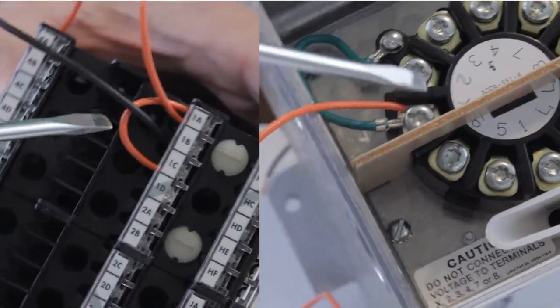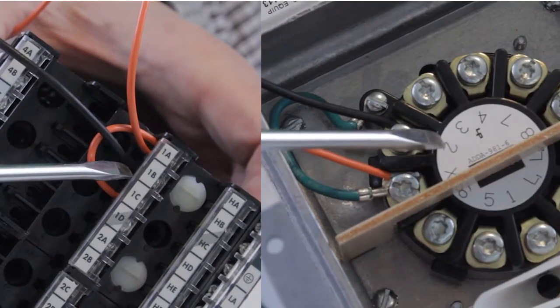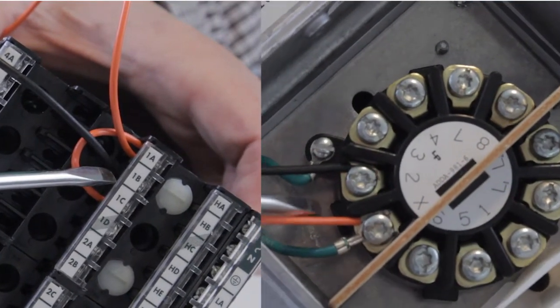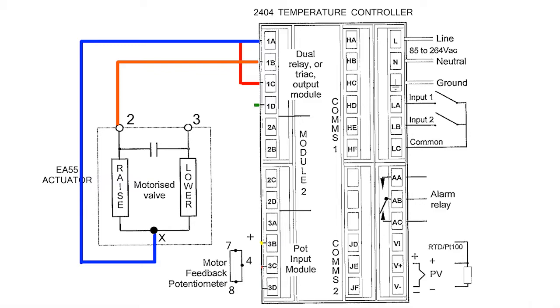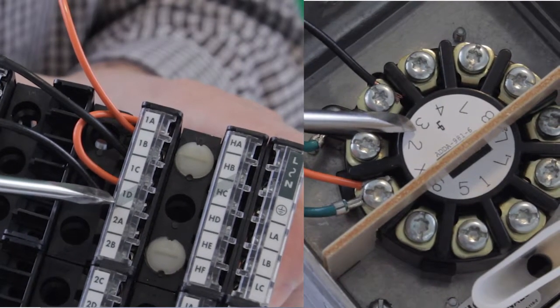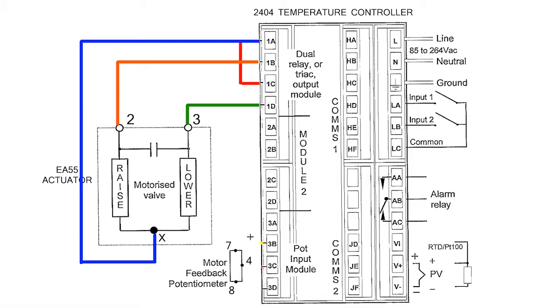Next, wire terminal 1B of the temperature controller to terminal 2 of the motorized valve actuator. Next, wire terminal 1D of the temperature controller to terminal 3 of the motorized valve actuator. This completes the output wiring for this style of control.